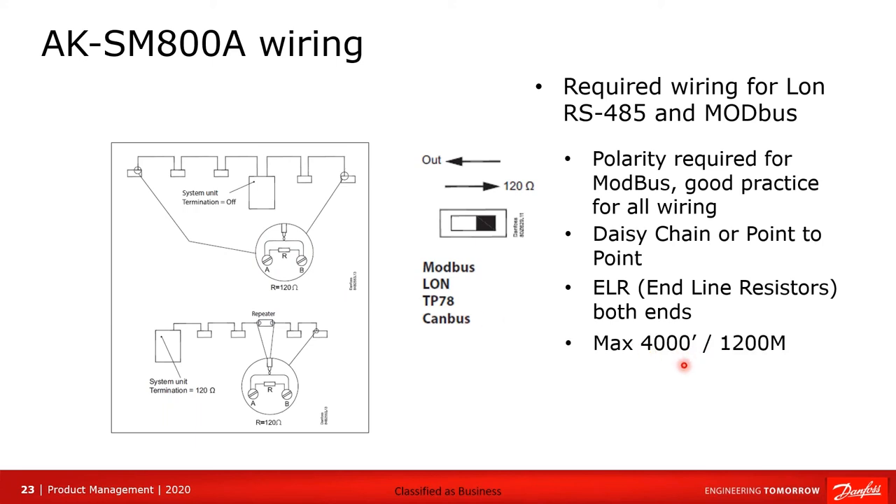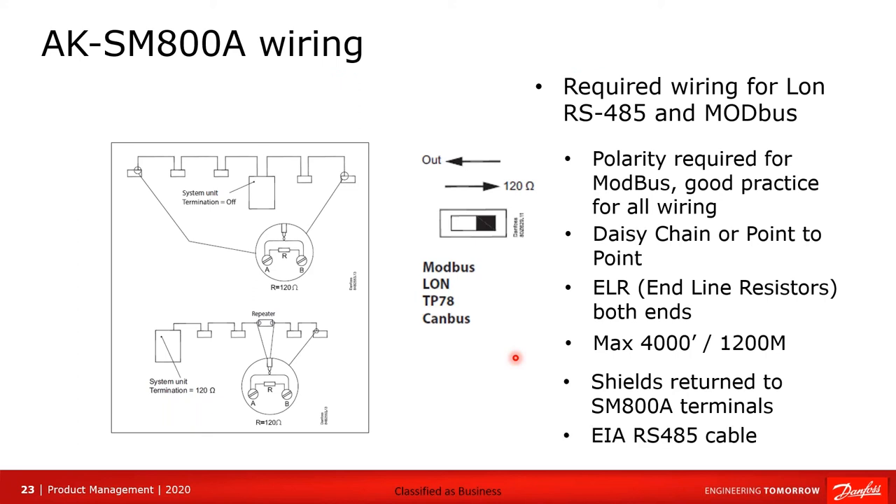The maximum length of your complete run on the LON network or MOD bus network is 4,000 feet. The shield must form a complete path and must return back to the SM800A, connected to the shield terminal. The cable to use is EIA RS-485, which has all the correct properties for the best operating network.